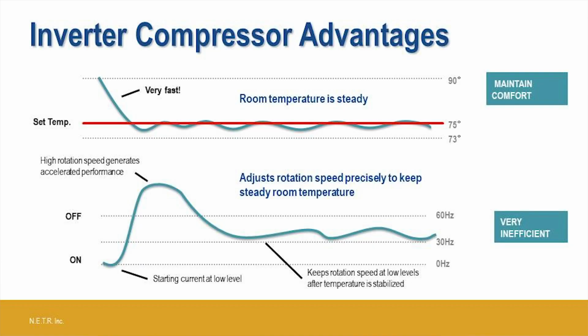Right here is where they're a very soft start compressor, and I'll show you this today, guys, of how a system starts up. It starts up on a very slow speed, and then it ramps up. And then it ramps back down again, and it's doing this with the room temperature right here. So when the room temperature is very warm, the compressor runs very fast. When the room temperature gets to the temperature set point of 70 degrees, it says, okay, just slow down and run at a very, very slow speed of cruise control. And you can see we knock out all the hertz on that, and that's how we pick up our efficiency.